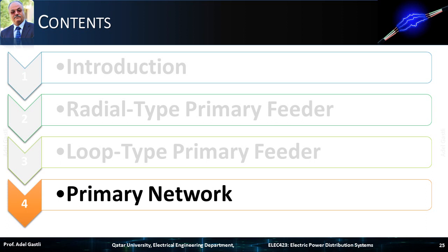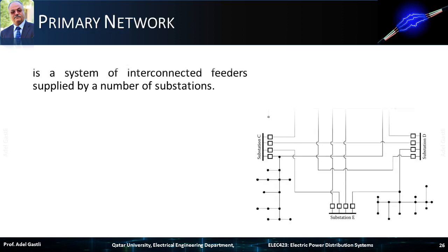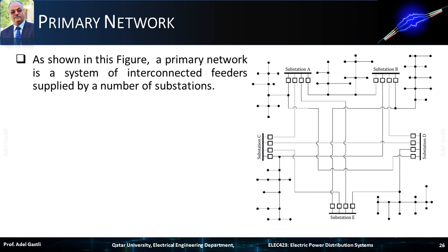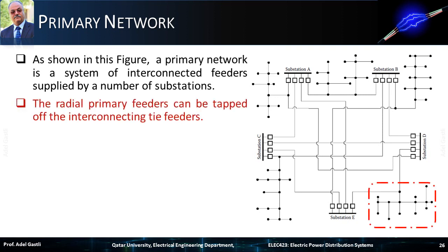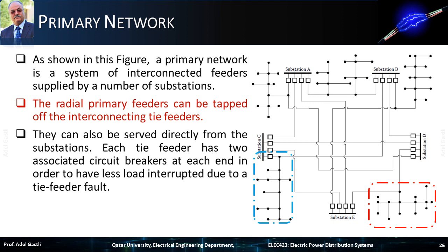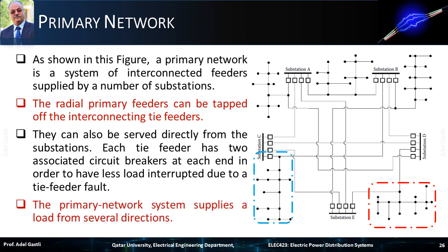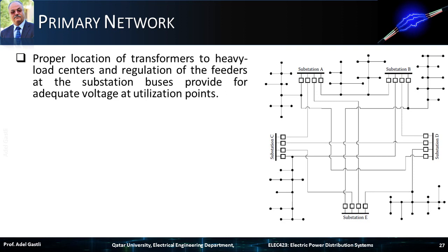Finally, let's consider the case of a primary network. As shown in this figure, a primary network is a system of interconnected feeders supplied by a number of substations. The radial primary feeders can be tapped off the interconnecting tie feeders, or they can also be served directly from the substations. Each tie feeder has two associated circuit breakers at each end in order to have less load interrupted due to a tie feeder fault. Therefore, the primary network system can supply a load from several directions. Proper location of transformers to heavy load centers and regulation of the feeders at the substation buses provide for adequate voltage at utilization points.